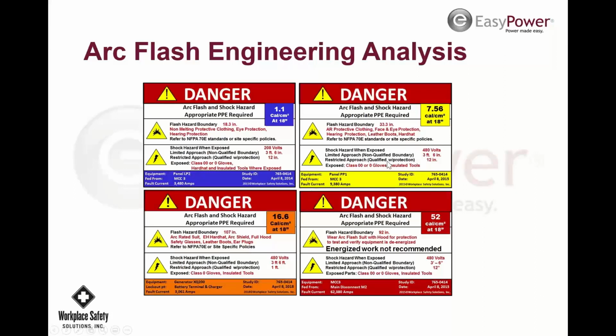I put some definitions for the approach boundaries so people remember what they are. I also put the fed by information so we know where to lock it out. And I also put the available fault current on the label. So that's one thing that NEC requires now. So I started doing this back in 2006, long before NEC required it. And then orange is over 8 and red is over 40.